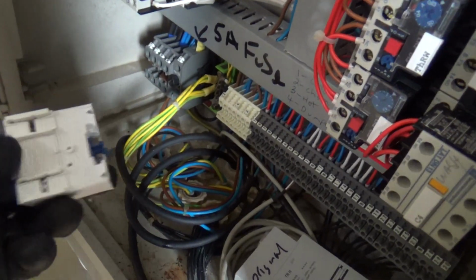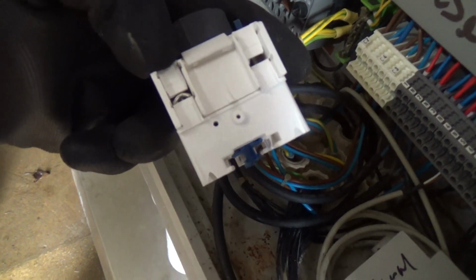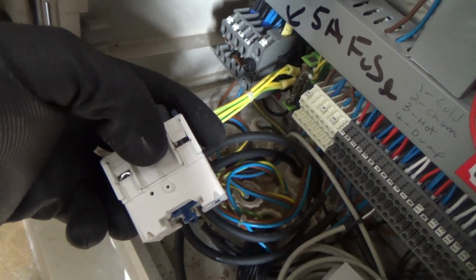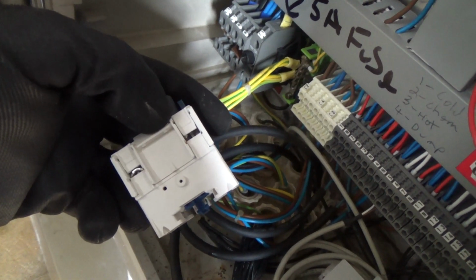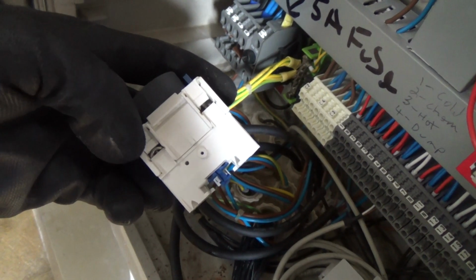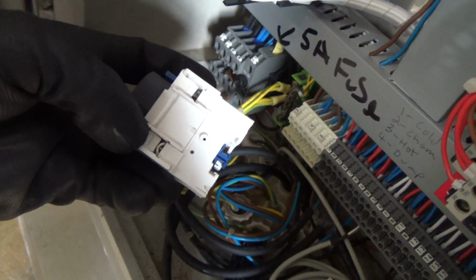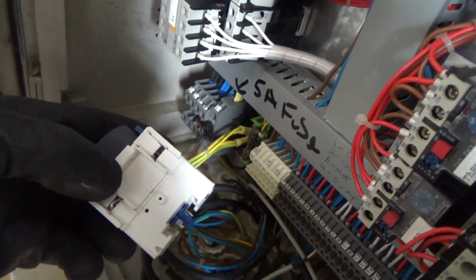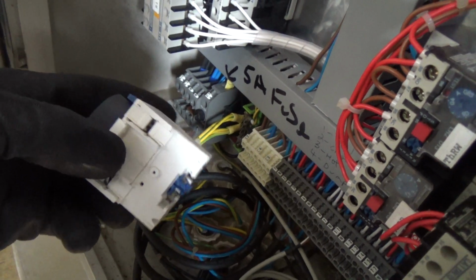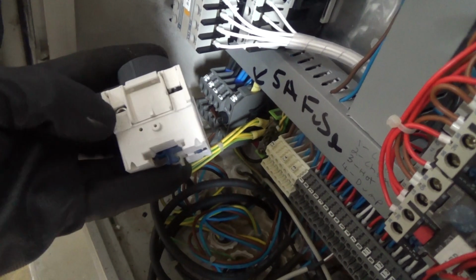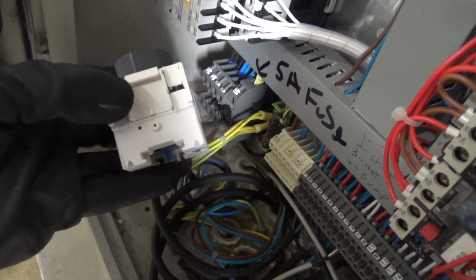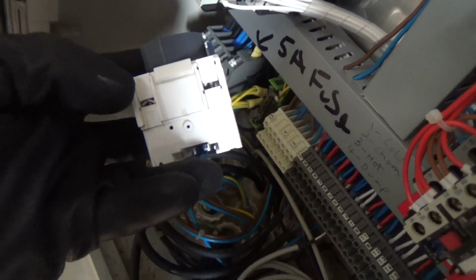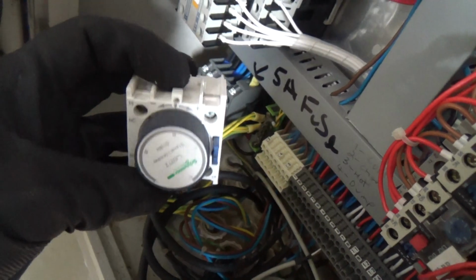So, anyway, what I've taken to doing is on the terminals you don't use, I wind the screws in, and that way, if you go to work on something and the wires come out for whatever reason, you've got a better idea - well, on this one you'd know it's got to have come out of that one because that one's tight, but it can help you narrow down where things should go back if they can't physically go there. It couldn't have physically come out of that one. Other things, I've seen them where the screws rattle loose and they can fall out, causing problems.